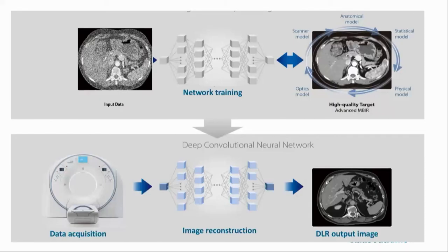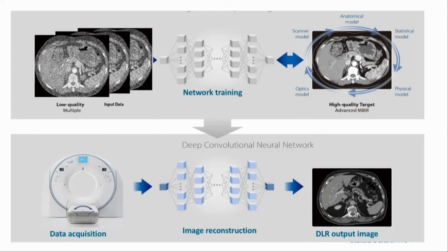How is it done? You take the highest quality images you can get — model-based iterative reconstruction with enough dose — and from that you create raw data of the same patient with high image noise. You reconstruct these images and then train a network to go from this noisy input data to the high-quality output data. You do this not only for one image but for thousands of images, or subgroups of voxels within these images. The training process is really slow and can take hours to weeks, but the ultimate reconstruction when you have a new low-quality data set is very fast and high quality.